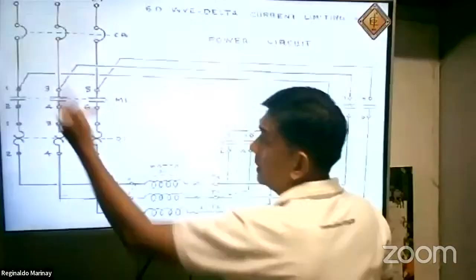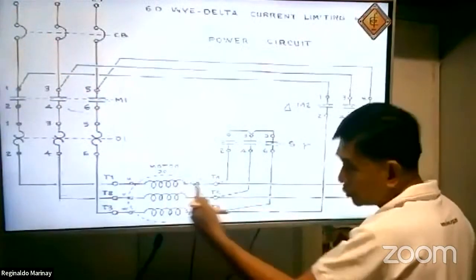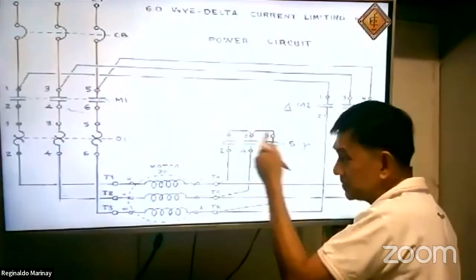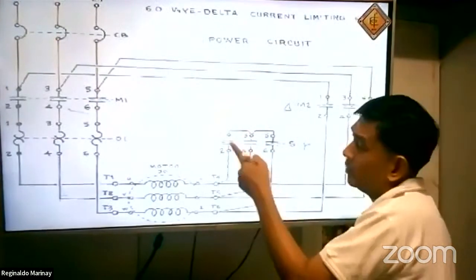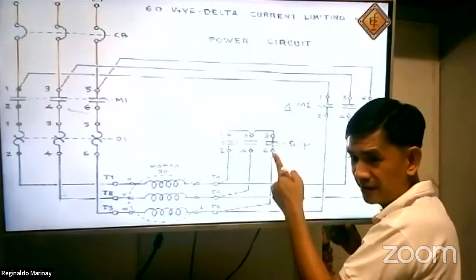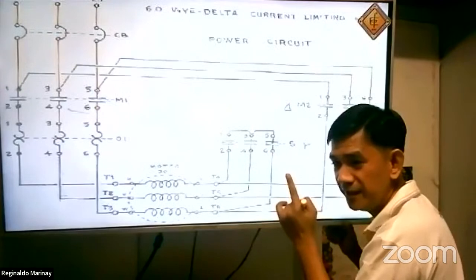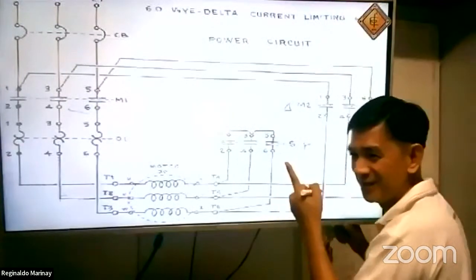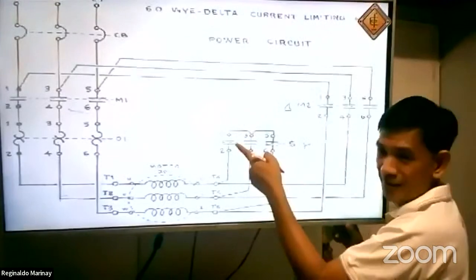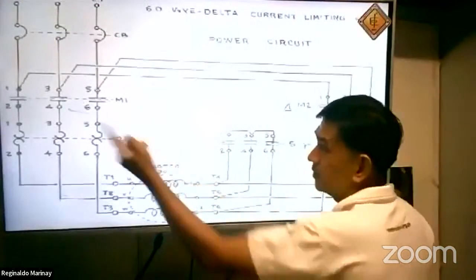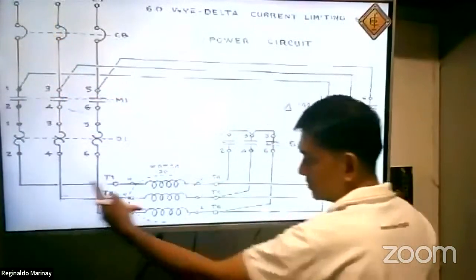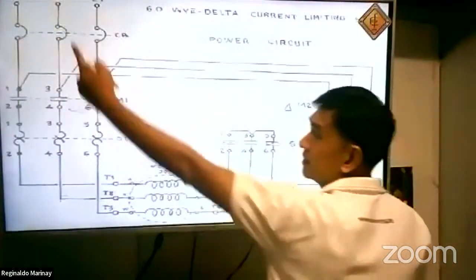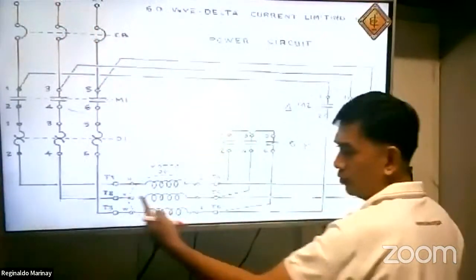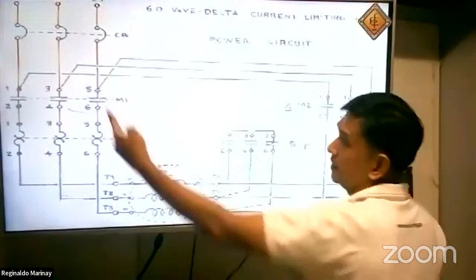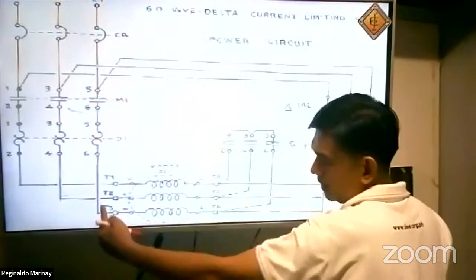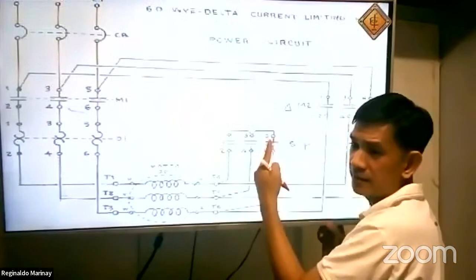Take a look here. Line 1, going to the coil to neutral. This 3 represents the neutral because this was held closed, isn't it? Are you getting me? So, this is closed. So, again, A, going to the coil, going to the neutral. The current will flow. B, going to the coil, going to the neutral. We have your C, it will flow here, then to the coil and going to the neutral.